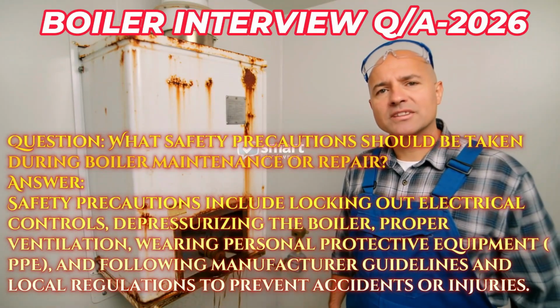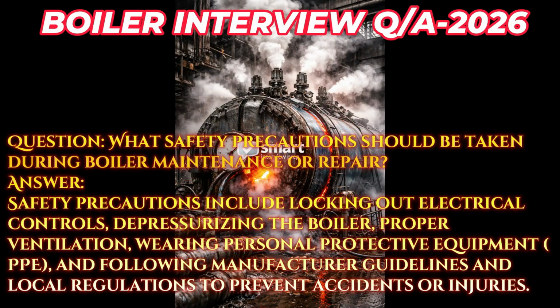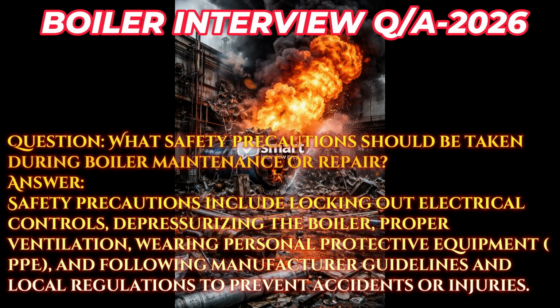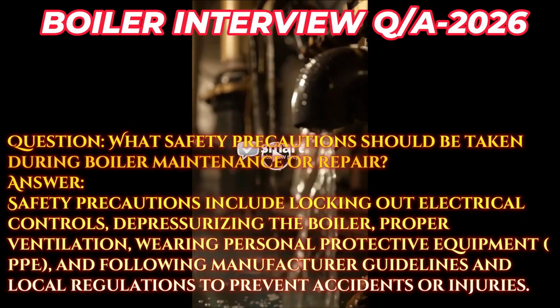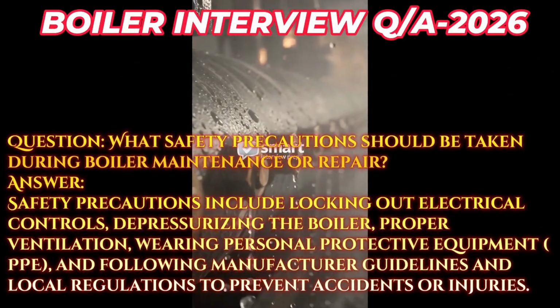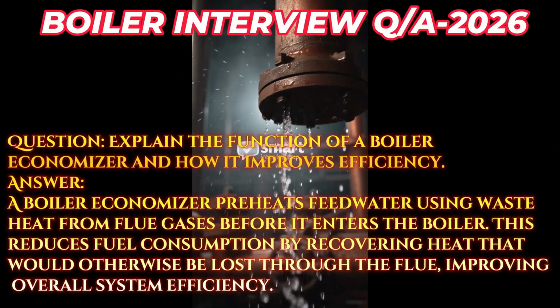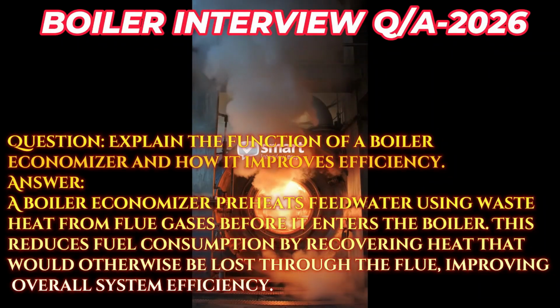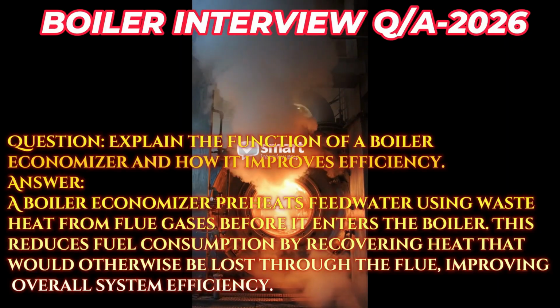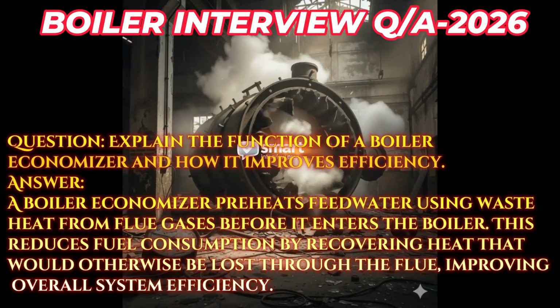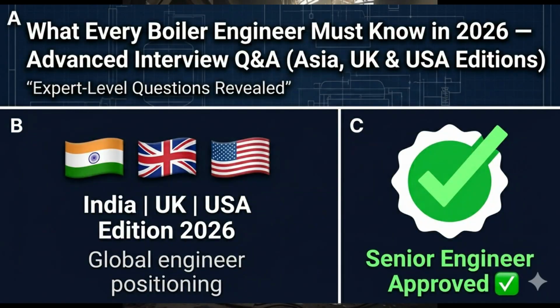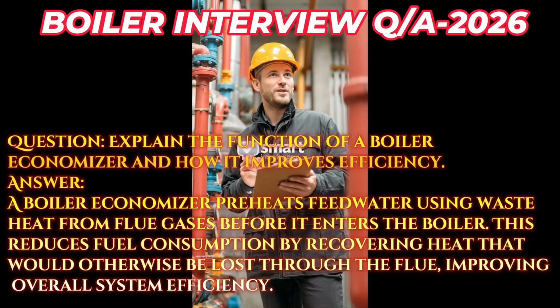Question. What safety precautions should be taken during boiler maintenance or repair? Answer. Safety precautions include locking out electrical controls, depressurizing the boiler, proper ventilation, wearing personal protective equipment, PPE, and following manufacturer guidelines and local regulations to prevent accidents or injuries. Question. Explain the function of a boiler economizer and how it improves efficiency. Answer. A boiler economizer preheats feedwater using waste heat from flue gases before it enters the boiler. This reduces fuel consumption by recovering heat that would otherwise be lost through the flue, improving overall system efficiency.